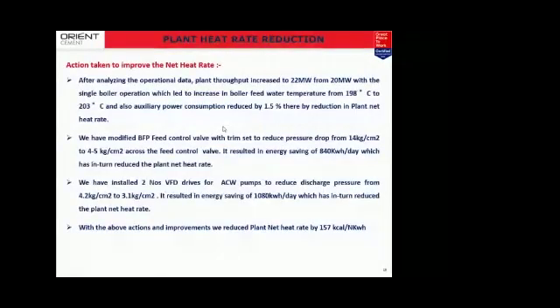So this is the slide where we want to showcase our heat rate reduction, how we have done it. Usually I just want to simplify a small thing: since we are a 2 boiler and a single turbine unit, based on our load demands, we are only operating a single boiler with the existing 45 megawatt turbine. When we are operating a single boiler, we can generate 94 TPH, 94 tons per hour of steam, which will be given to the turbine.